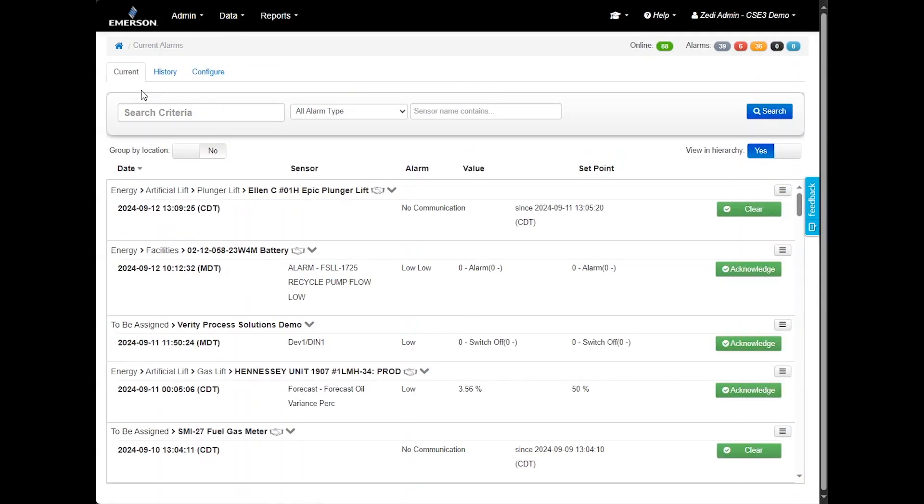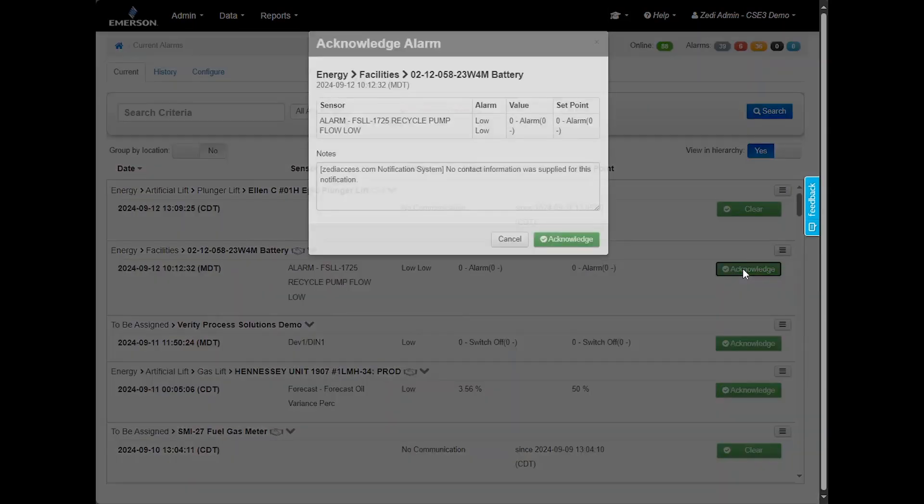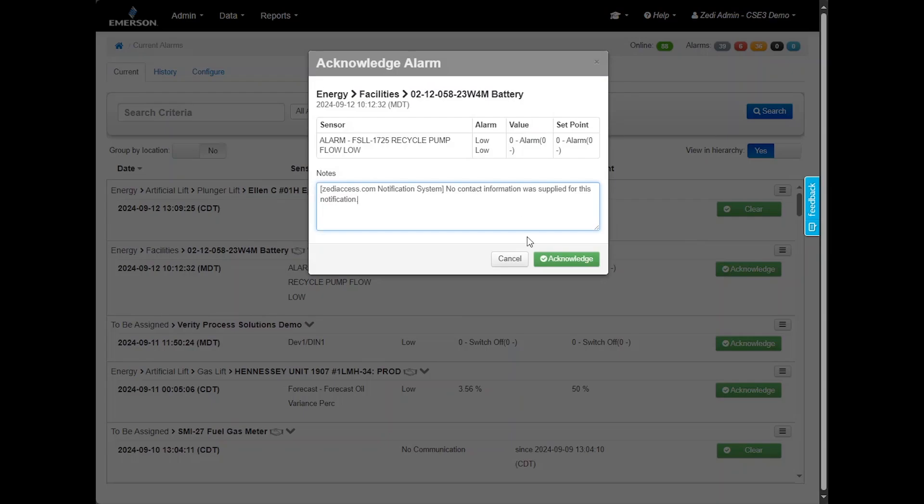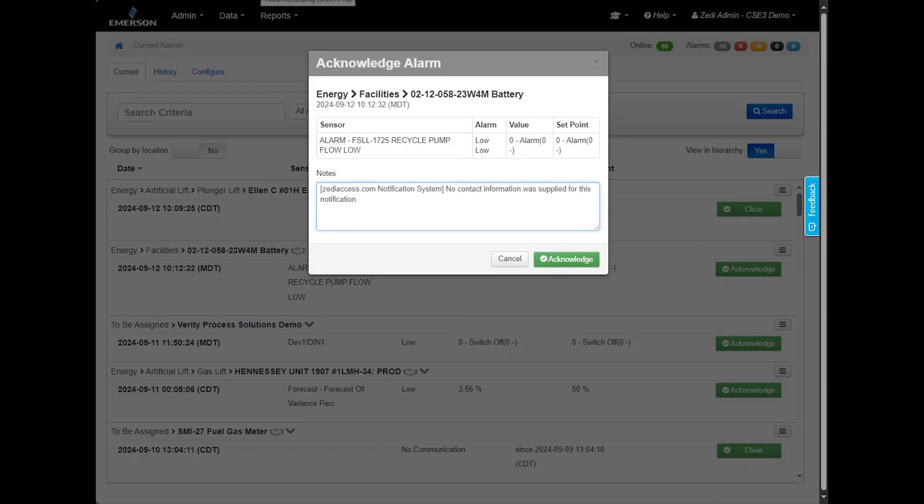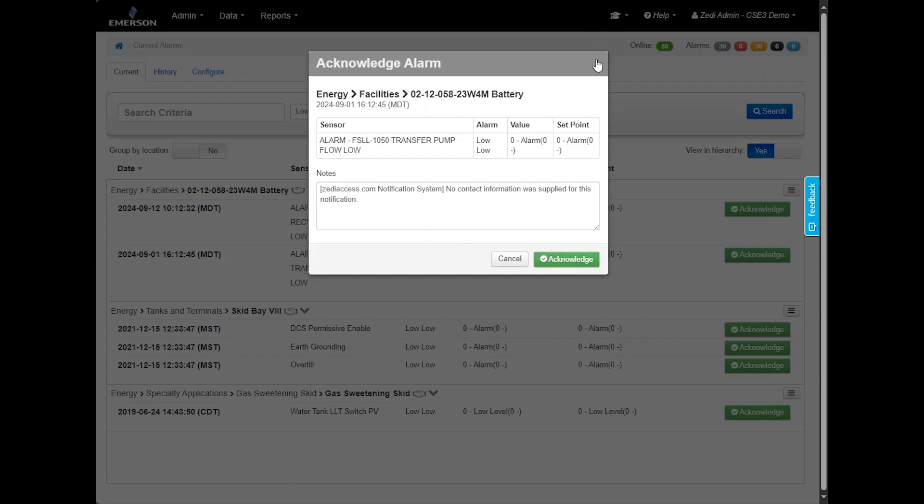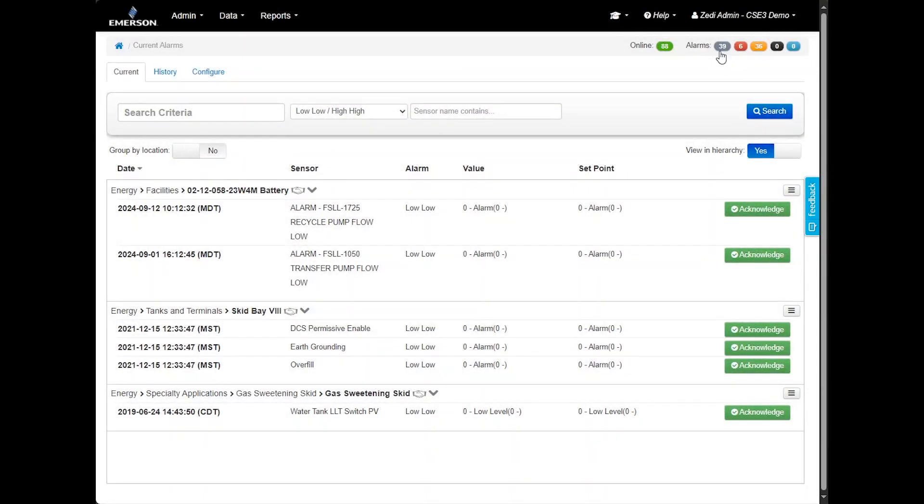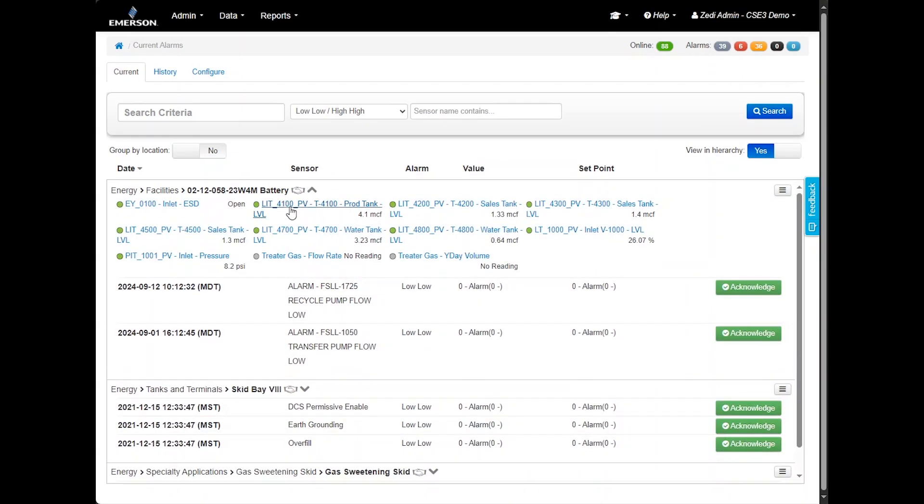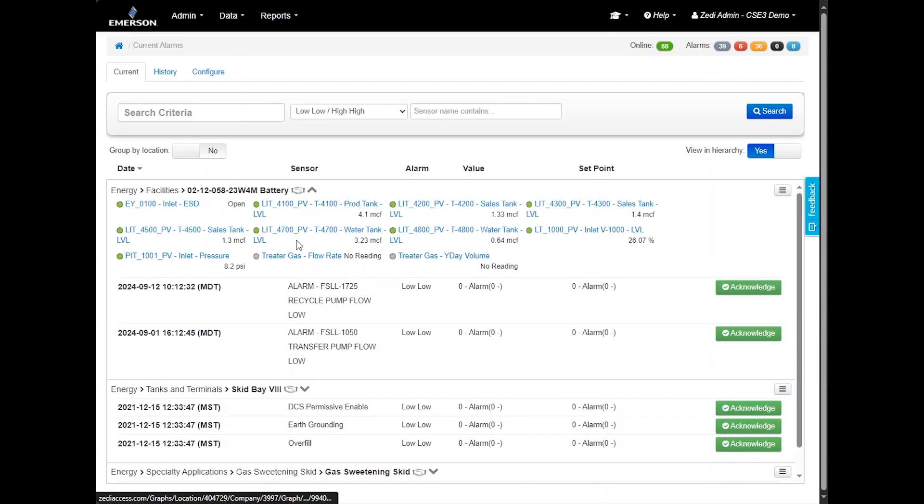On the current alarm tab, you can view, acknowledge, or clear alarms. When you select acknowledge, a pop-up window will appear where you can optionally add a note. While adding a note is not required, it helps track which user has acknowledged the alarm. Once an alarm has been acknowledged, it will be removed from the dashboard notifications. However, if the alarm condition persists beyond the set parameters during the next polling cycle, it will reappear on the site display.